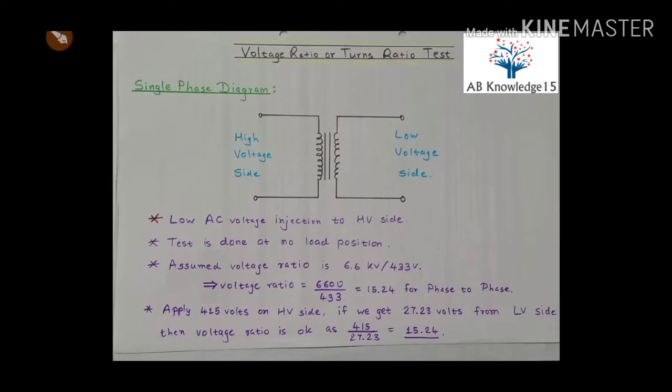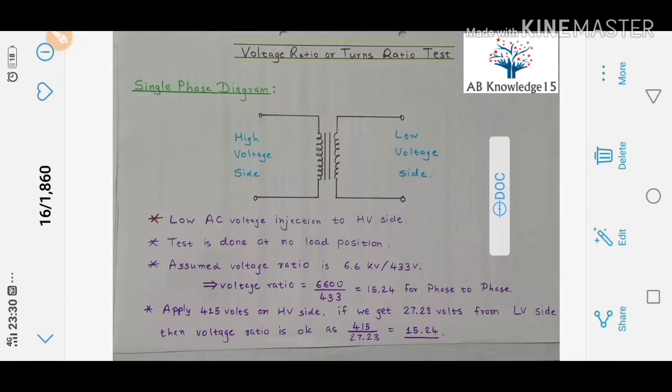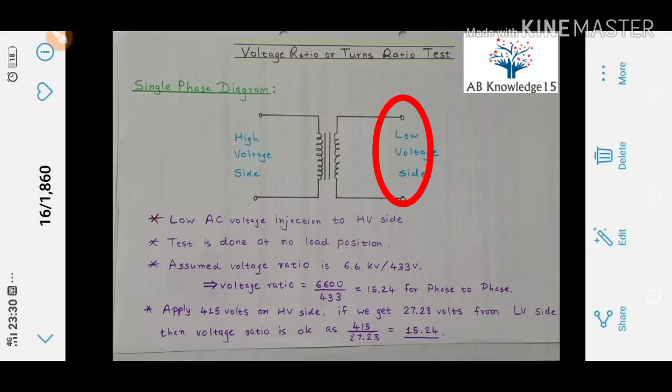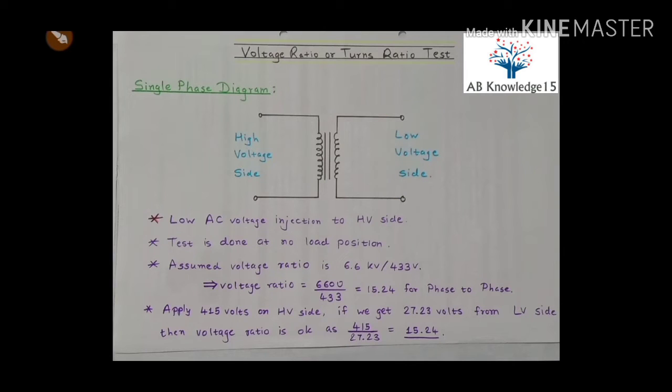We will understand this voltage ratio test procedure by this single phase diagram of transformer. Here this is the high voltage side and this is the low voltage side. We are injecting low AC voltage to high voltage side of transformer. Why? Because as per the voltage ratio of the transformer, if we are applying low AC voltage, the secondary side voltage will also be low comparing to the primary side, and that is for the safety purpose.